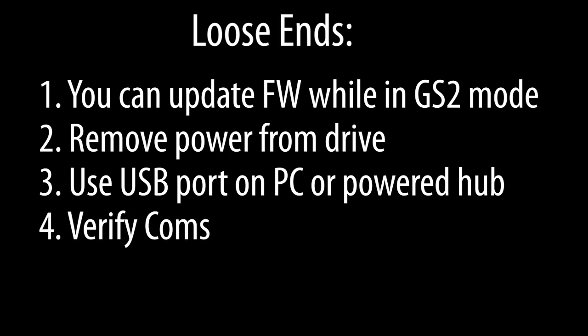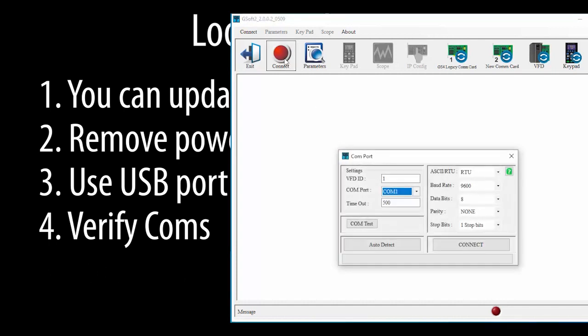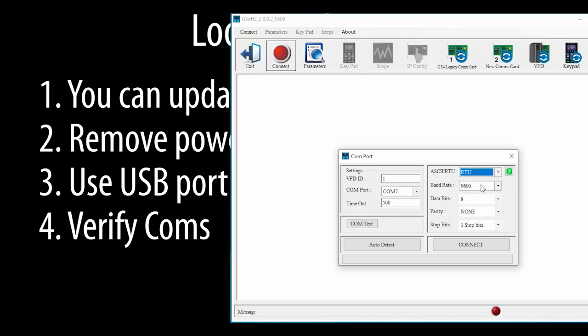I like to verify my comms before doing a firmware update. Just go to the connect dialog, choose the comm port you are using and make sure this is set to RTU. Hit Comm Test. If you get this green OK, then comms are good. Now don't hit the connection button. You don't want to be connected to the drive while doing a firmware update.